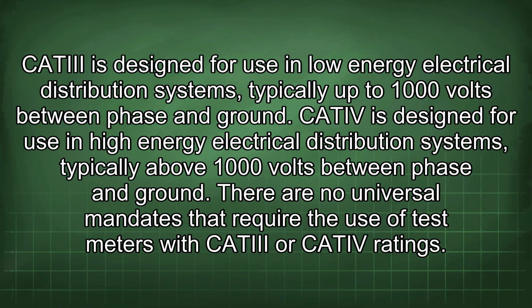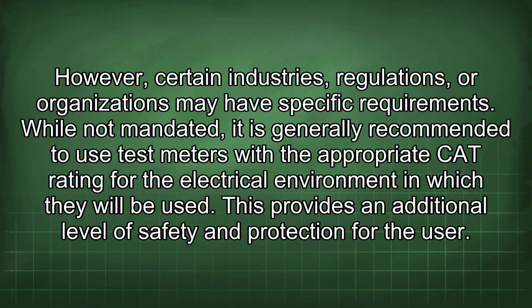There are no universal mandates that require the use of test meters with CAT III or CAT IV ratings. However, certain industries, regulations, or organizations may have specific requirements. While not mandated, it is generally recommended to use test meters with the appropriate CAT rating for the electrical environment in which they will be used. This provides an additional level of safety and protection for the user.